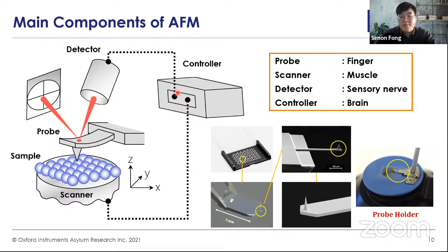The cantilever is made of flexible material. When we push the cantilever onto the sample, the cantilever bends. The bending is measured by an optical lever detection system, consisting of a laser diode and a photodetector system. In order to get an image, we need to move the sample or the probe, and we can move that using what we call a scanner, in X, Y, and also Z directions, with a feedback mechanism which is not listed here. The signals are collected, then processed by an instrument called a controller. Basically, it is considered the brain of the AFM. Here are a few examples of images captured using an AFM. All of these images are topography, which in AFM terms we call a height image or height channel.